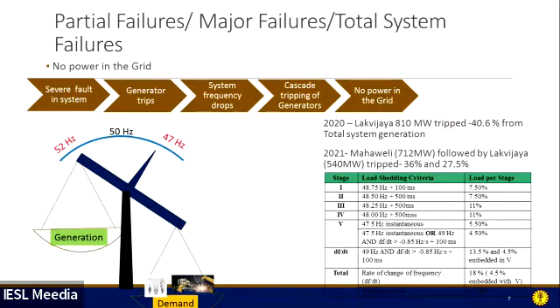Right. So what happened in 2020? There is a reason. There was a three-phase earth fault at Kerawalapitiya, a severe fault. That is the reason, and generators tripped. 810 megawatt was lost from the system, so the system failed. At that time, the total generation loss was 40%.